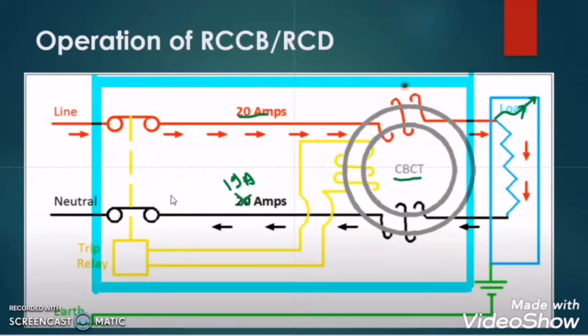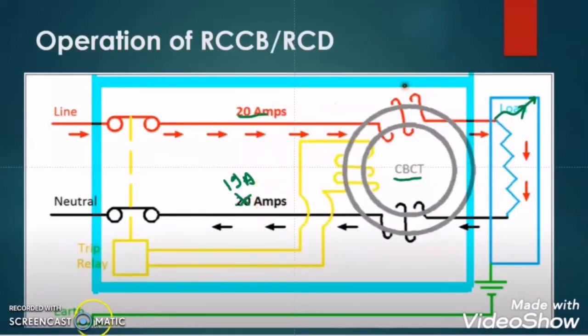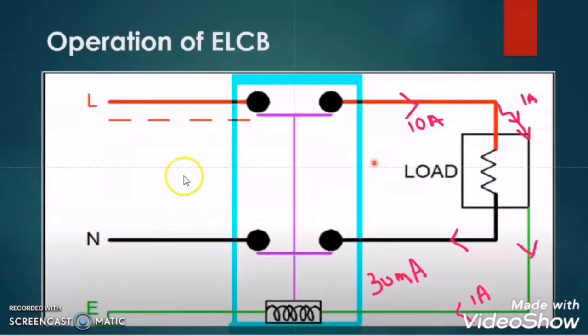One very important point to observe: in the case of ELCB, the earth conductor plays a vital role in tripping. The leakage current flows through the earth conductor and activates the tripping coil of the ELCB. But in the case of RCCB, there is no role of the earth conductor. Even if there is no earth conductor, the RCCB will still trip.